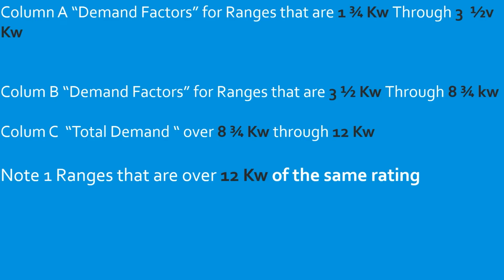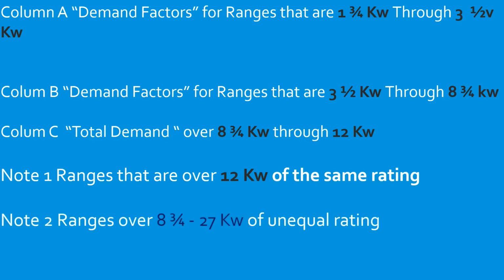And that sounds really complicated, but I break it down in the future slides and you'll know exactly how to do it, no problem. Now let's go ahead and look at note 2. This deals with ranges that are 8 3/4 or more through 27 of unequal ratings. And what it tells us to do is to average out a value by adding all of the ranges together to make a total connected load. We have to use 12 kW as the minimum for each range, then divide that total by the number of ranges, and then the maximum demand of column C shall be increased by 5%. So I'm going to teach you how to do that.